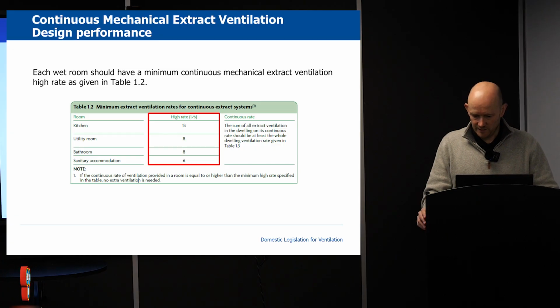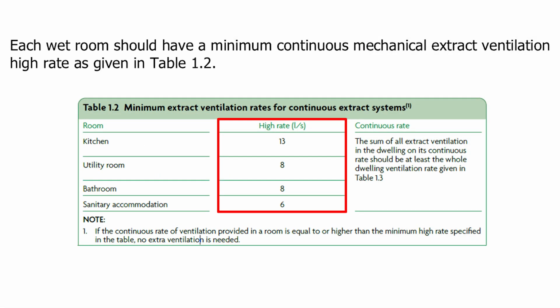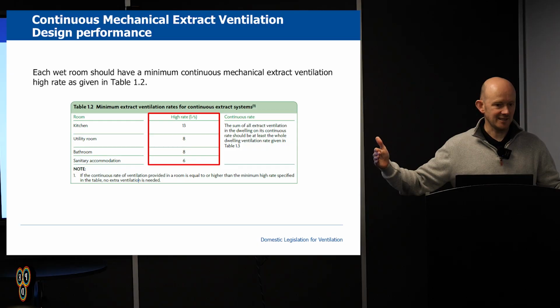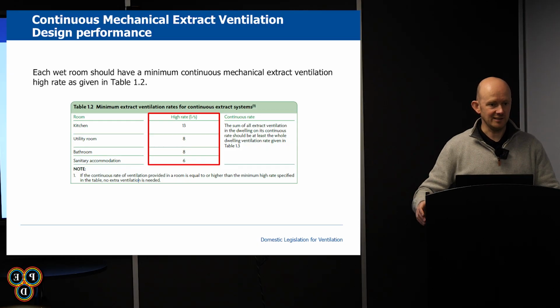It's a bit late. For MEV and DMEV systems, we have to look at the high rate, the boost speed, and also the continuous rate, the background trickle rate. The minimum high extract rate is defined in litres a second for each of the wet rooms. Kitchens 13, utility 8, bathroom 8, sanitary 6. That is the boost rate, not what it runs at continuously. We and others can design a space and say what it needs to trickle at and tell you. But if that space is a big space, you might be trickling at 15 litres a second, which means the boost will be 15 litres a second.